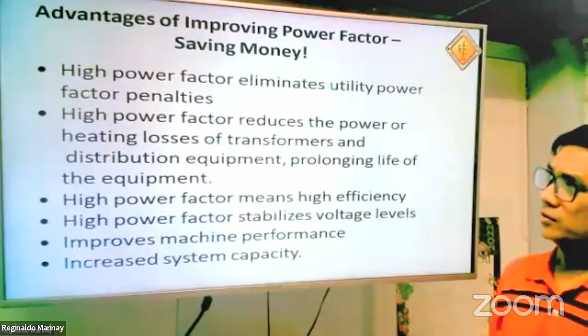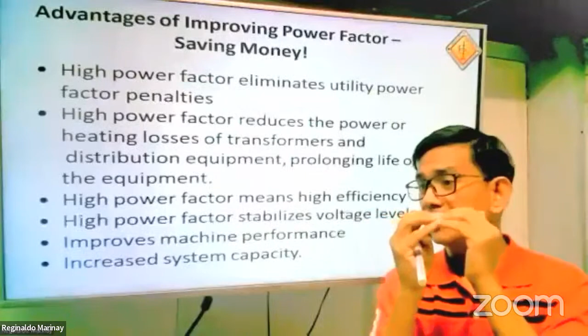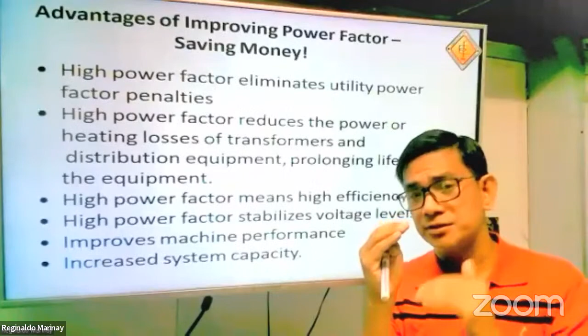These are some advantages of having an improved power factor. The number one, the greatest contribution of power factor correction, is saving money. This will cut your electric bill. A high power factor eliminates utility power factor penalties. If you go lower than a certain base power factor, for example, here in our country the biggest electric utility company, Meralco, has an 85% maintaining power factor. A building must maintain that 85%. Lower than 85%, there will be a penalty or surcharge; higher than 85%, you get a discount from the utility company.